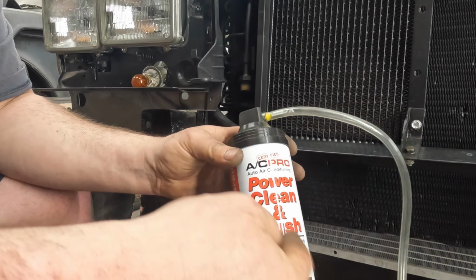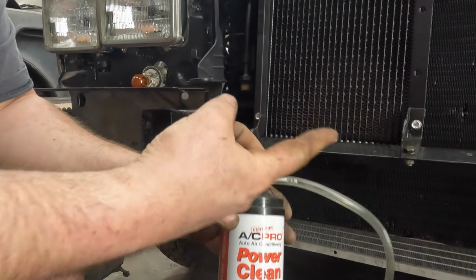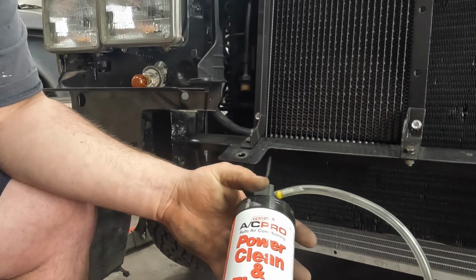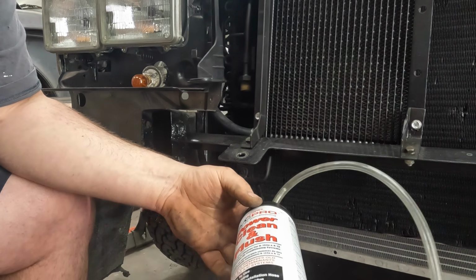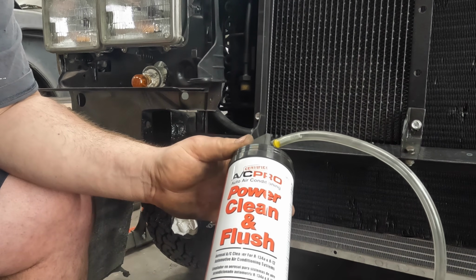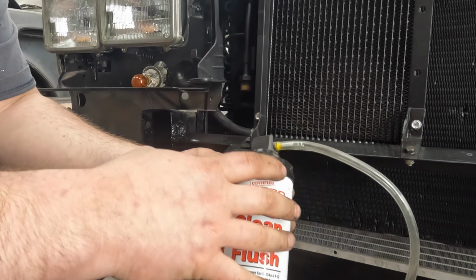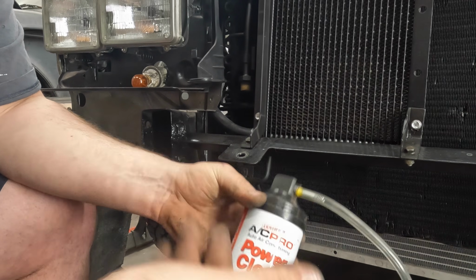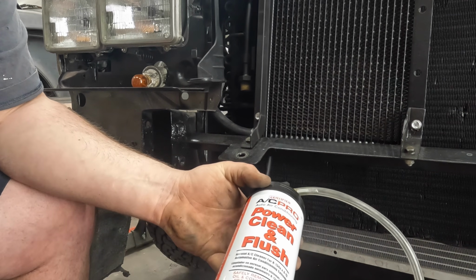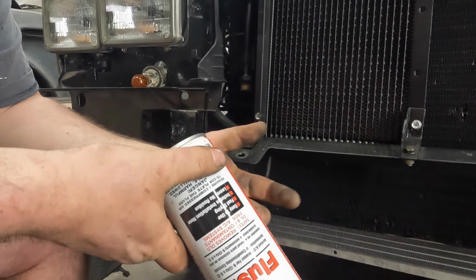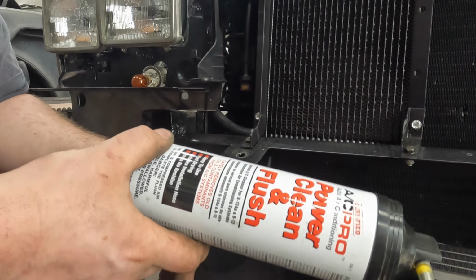Now this stuff is great, but you can only use it if, one, you're going to blow through it with compressed air afterwards, and two, you have a vacuum pump to suck down the system, because this is designed to evaporate off under vacuum and leave no residue, which is why it is specific AC stuff. I don't know what brands are around anymore. This is a couple years old, but should work good enough.